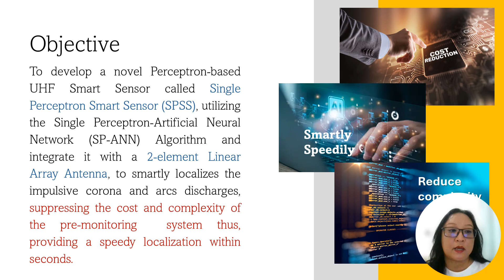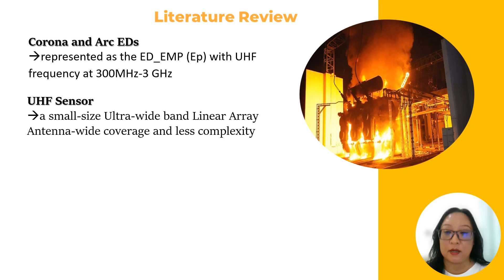Based on the review I have made, corona and arc discharge is represented as ED, electromagnetic pulse, or EP, with a UHF frequency in the range of 300 MHz to 3 GHz. For the UHF sensor, a small-size ultra-wideband linear array antenna is used due to its wide coverage and less complexity. Then for the perceptron artificial neural network algorithm, an adaptive ANN algorithm is developed to electronically smart beamform the linear array antenna radiation.